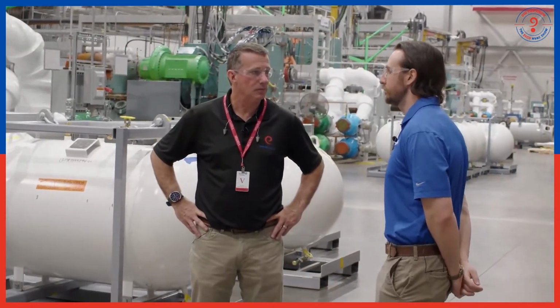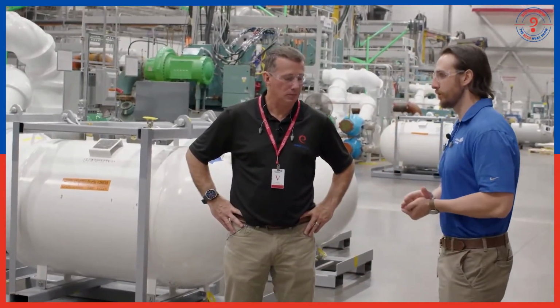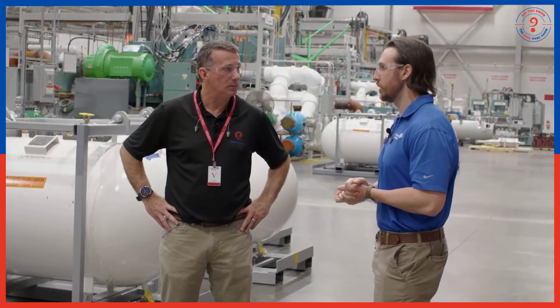So any highlights? What's been the biggest change that we've seen in the water-cooled arena in the last few years? The refrigerant change was a large one. Everything had to be redesigned for the new refrigerants that we have to use. So any product that used 134A had to change to 513A. Okay. Or we also have the zero GWP refrigerant 1234ZE available for some of our products.